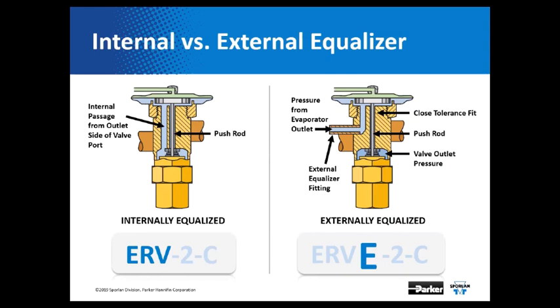Following the refrigerant code we have the internal versus external equalizer. In this example we have two different valves of the same family. The first is an ERV-2-C: after the ER body type we have the V refrigerant code — V is for R-22 — and since there is nothing after this V, we know this is an internally equalized expansion valve. On the right by comparison, we have an ERV with an E present, indicating it is externally equalized. You can physically see this on the expansion valve: you'll have an inlet port, an outlet port, and a third port which is the external equalizer.